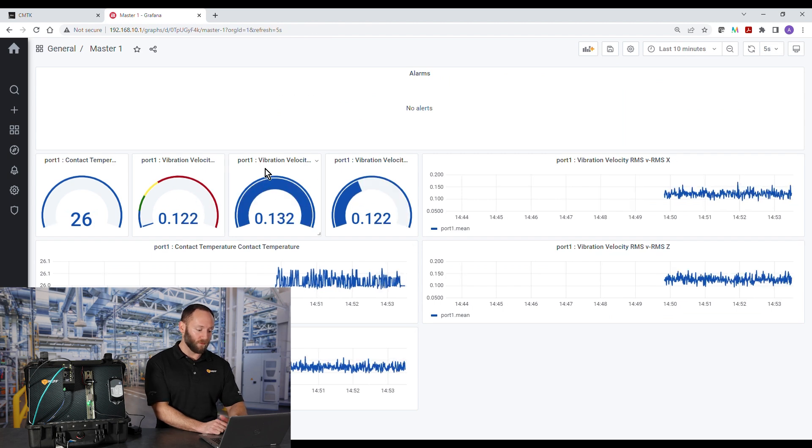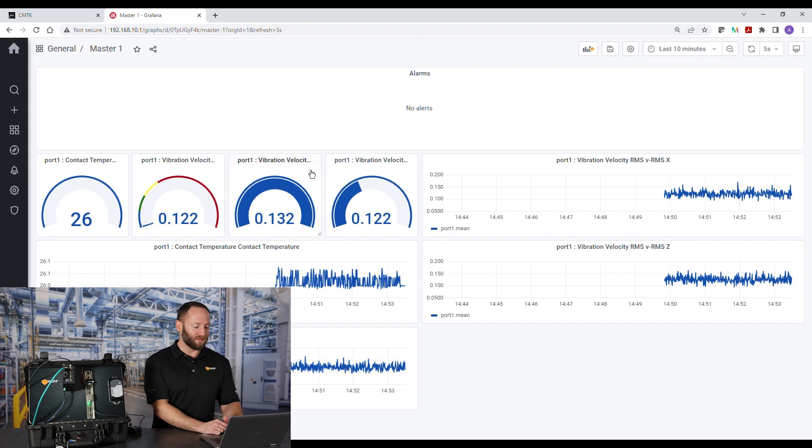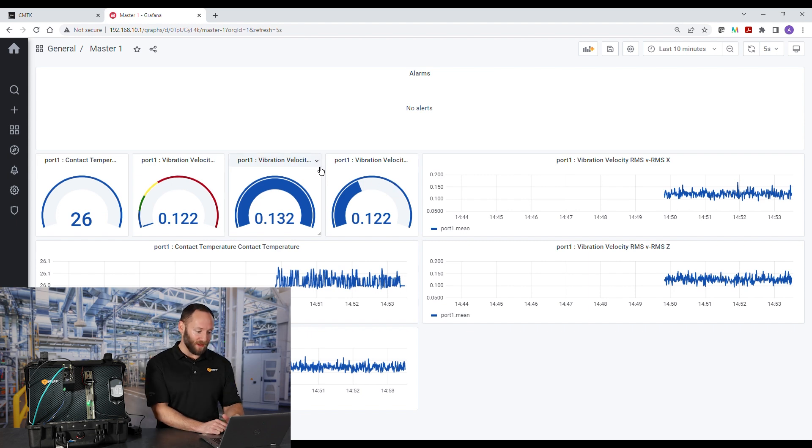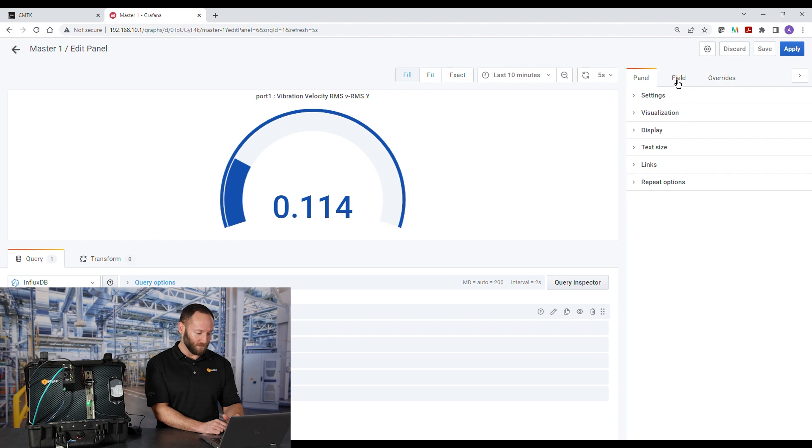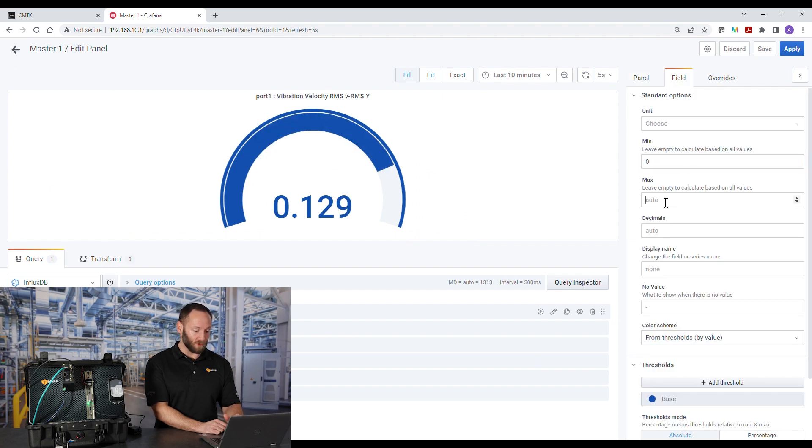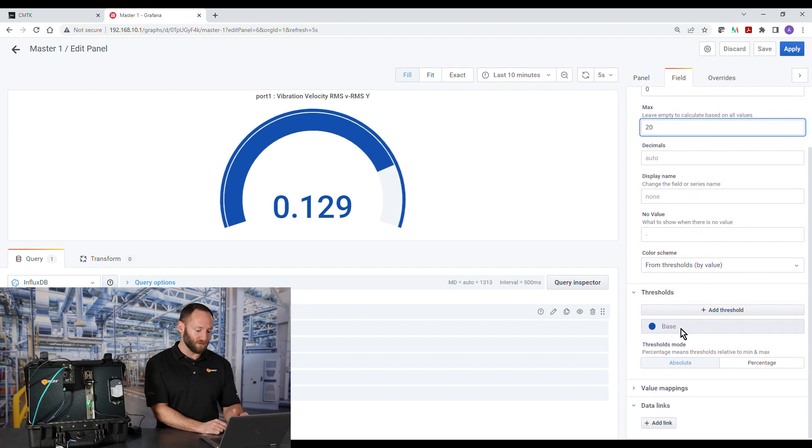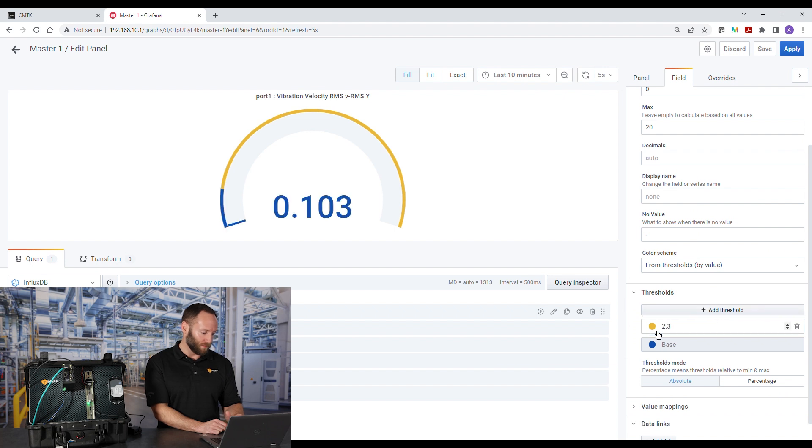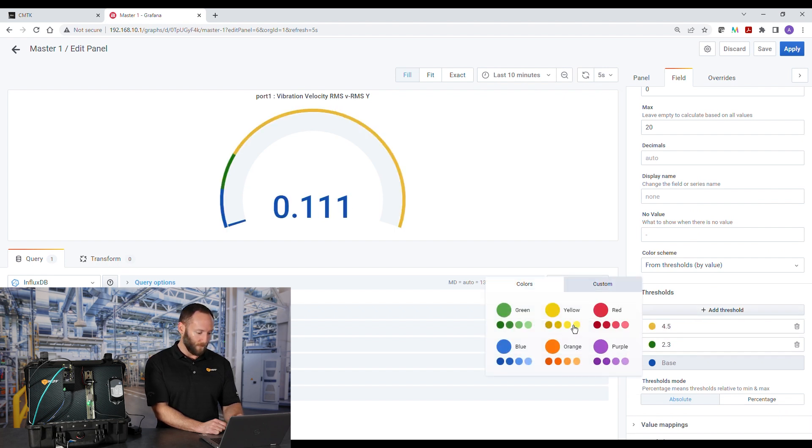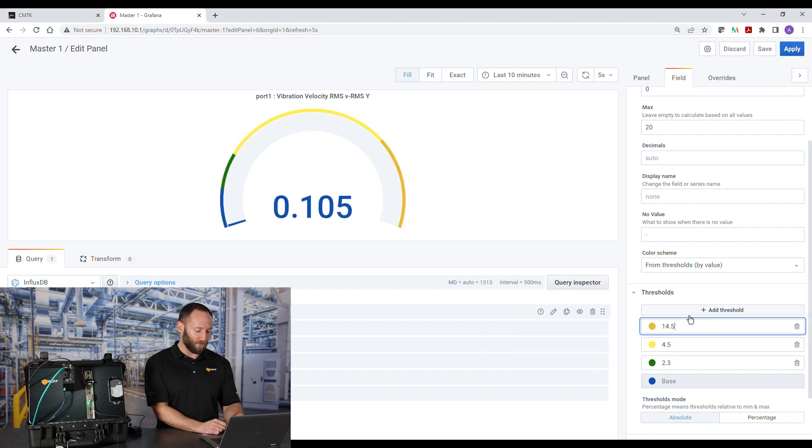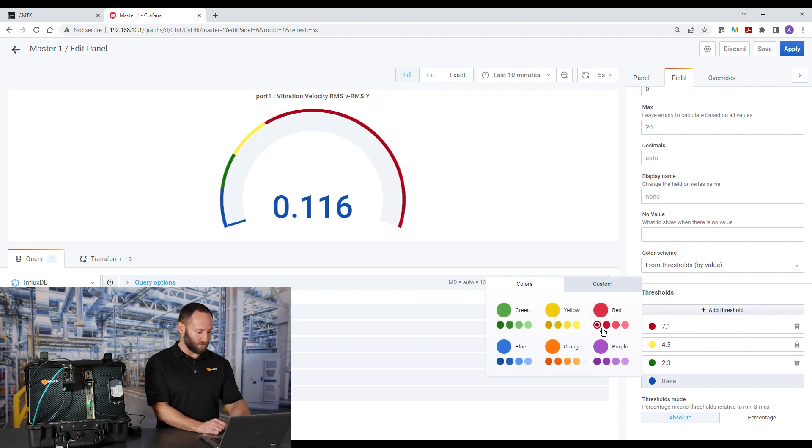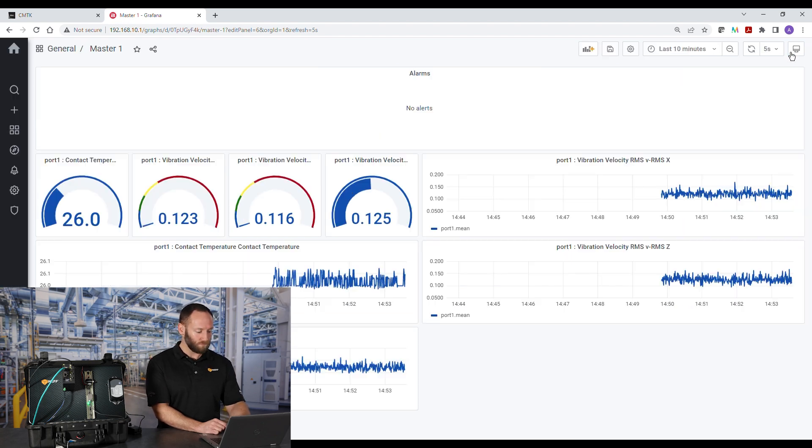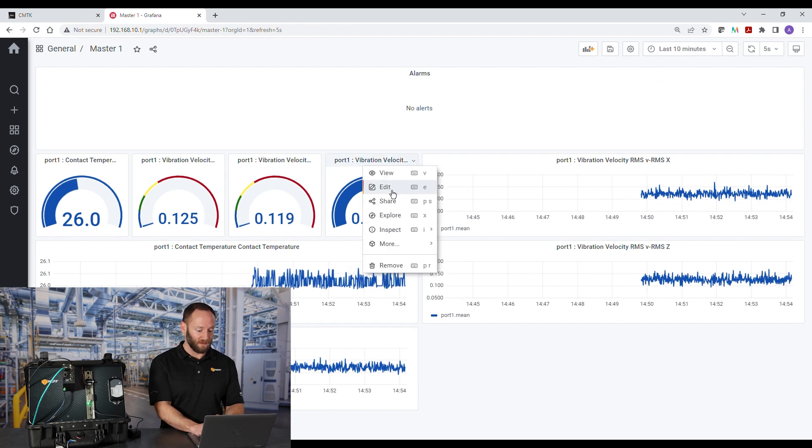That only impacted one gauge, so we're going to quickly do the same for the other gauges. Again, drop down menu, edit, field, scale, fixed scale, from 0 to 20 millimeters per second, user defined. Next, we'll add thresholds, severity zone B, green, severity zone C, yellow, and last severity zone D, and the color red. Then we'll repeat for the Z axis.